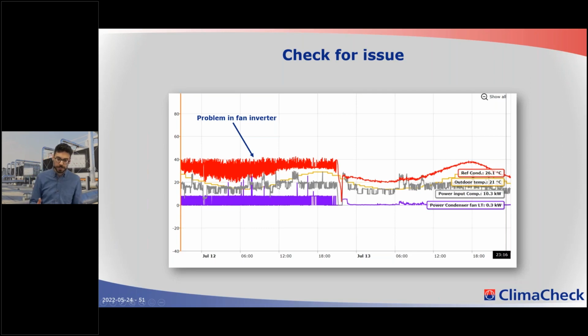Now, remember, this is a system that has been optimized. We've done quite a lot of analysis already. Our partner has been there, fixed with the contractor and so on. And this is happening after a year or so. We're on an optimized system. It is not uncommon to get frequent issues even on an optimized system. And it's important to continuously monitor to catch these issues. Now, at this point, we got an alert of high energy consumption compared to what we had predicted. And what we have is an issue in the fan inverters. And at this point, the contractor has been there and fixed the issue.